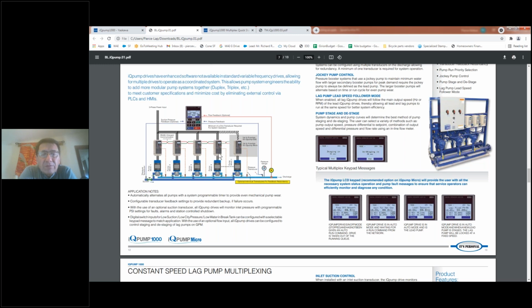wouldn't be putting variable frequency drives into this scenario if we weren't intending to vary the speed and therefore vary the output. Again, I will say that if your output requirement is steady, size a pump to run at full speed to handle it, and don't bother putting a drive in there because it's just going to cost you extra money and the drive won't give you any benefits. But in this case, we're going to assume 500 to 600 horsepower average load. We're sizing up to 800 horse.